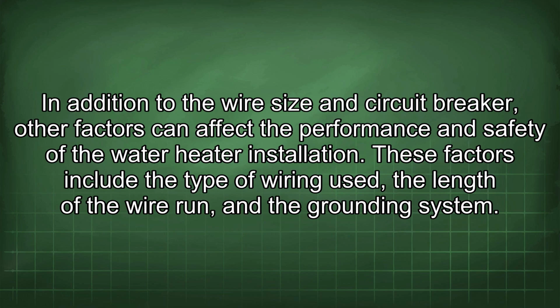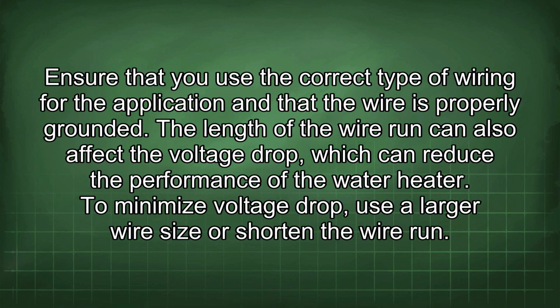In addition to the wire size and circuit breaker, other factors can affect the performance and safety of the water heater installation. These factors include the type of wiring used, the length of the wire run, and a grounding system. Ensure that you use the correct type of wiring for the application and that the wire is properly grounded. The length of the wire run can also affect the voltage drop, which can reduce the performance of the water heater.